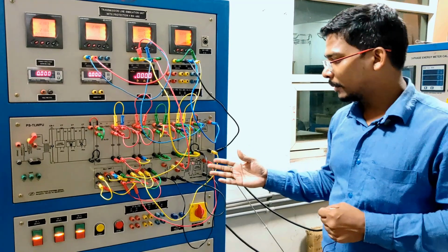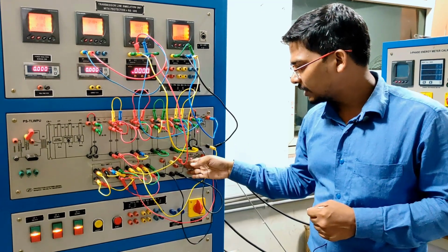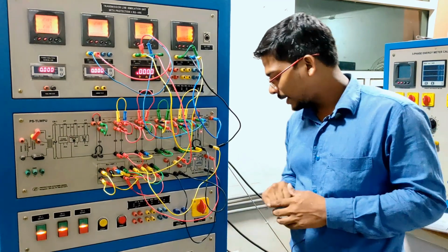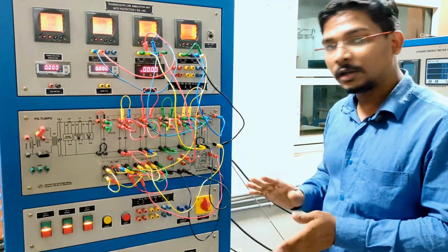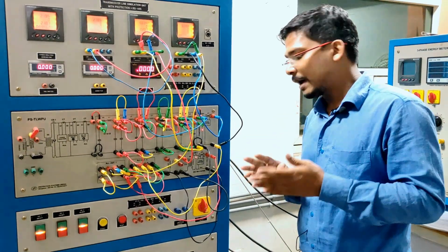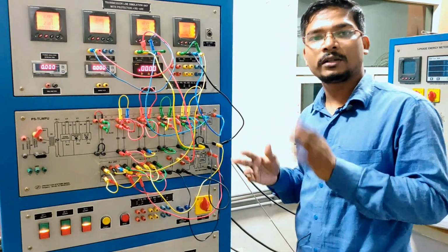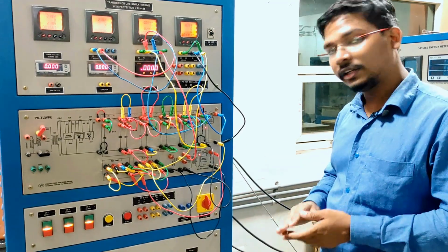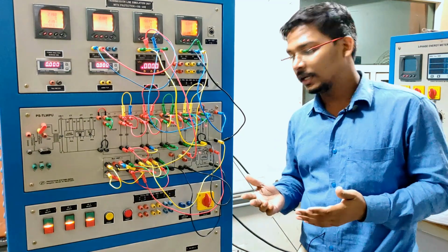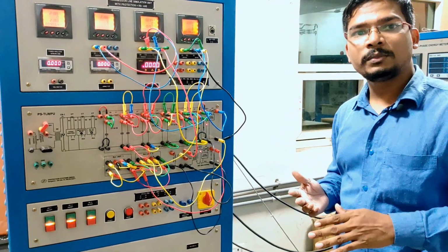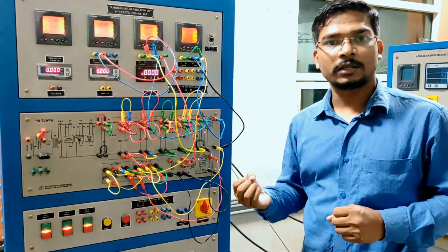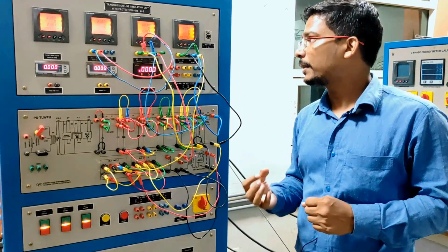Now with the use of this tap changing transformer, as you have observed, after 100 watt of load we have to turn on the capacitor. Earlier, after 200 watt of load we had to turn on the capacitor. Right now, after 100 watt of load, we have to turn on the capacitor. One advantage here is that if a capacitor is the compensator, then there will be no loss in the resistor. So there will be less power loss.